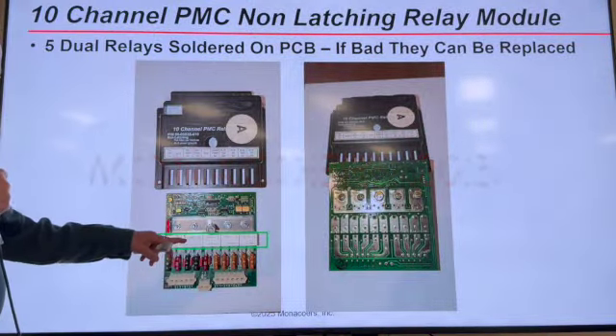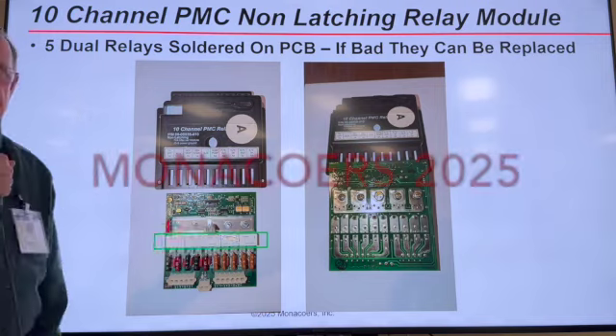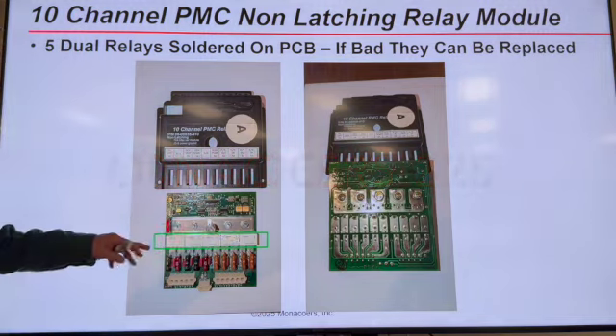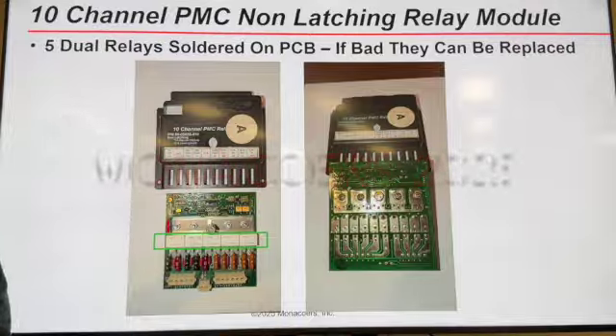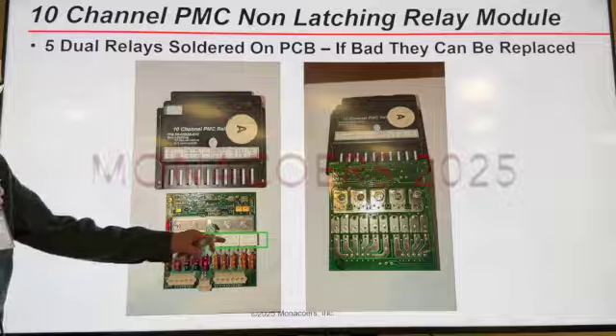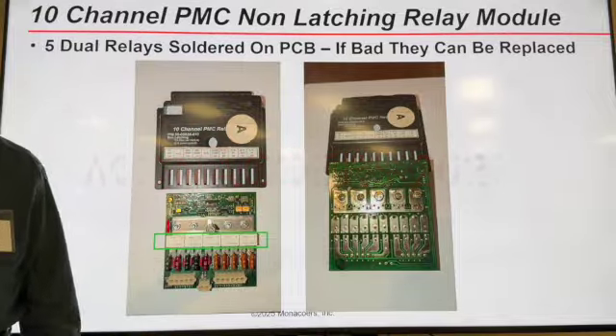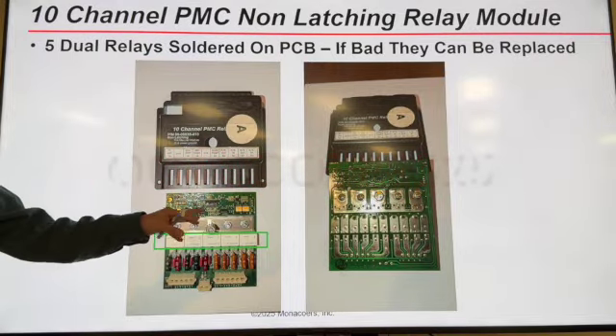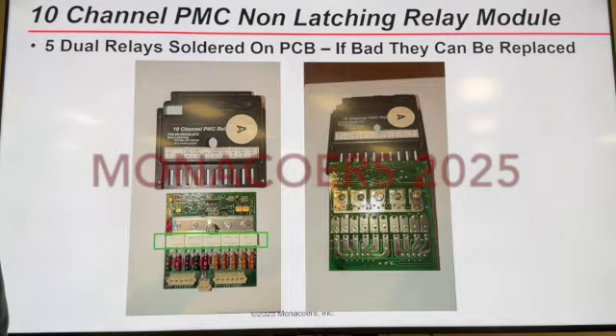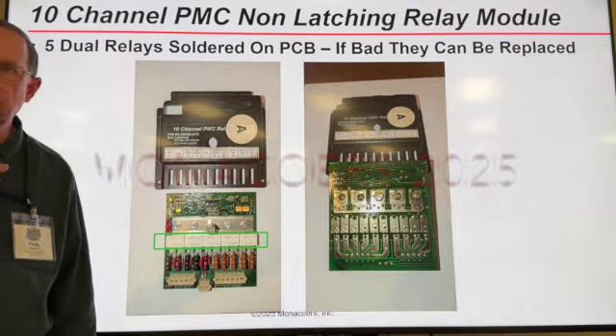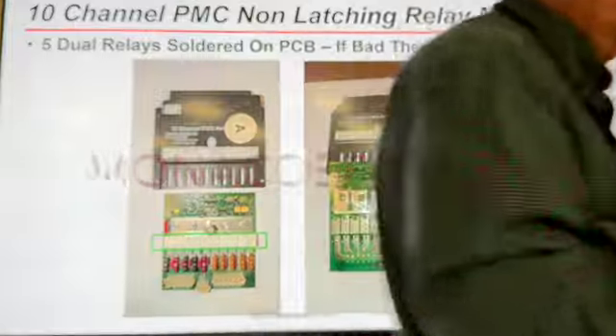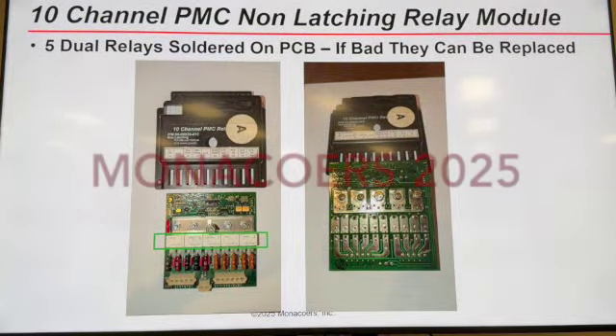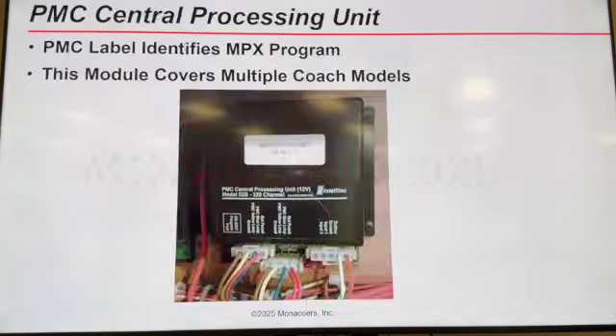These are dual relays, no longer available, so in order to repair this board we actually have to put in single relays, 2 single relays, to do the repair. I've tried to get these relays, couldn't get them. So when some of these boards go bad, Paul and I have looked at repairing them. Most all the components in here are still sourced, so if you get a bad one, don't throw it away. Even if you find a good one, save that bad one, because eventually we're going to run out of inventory.